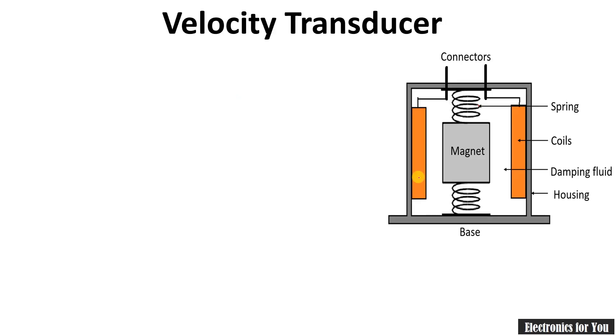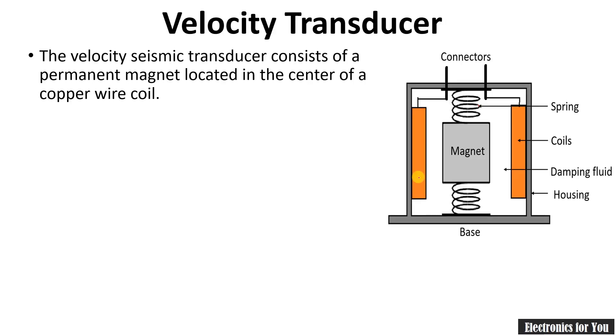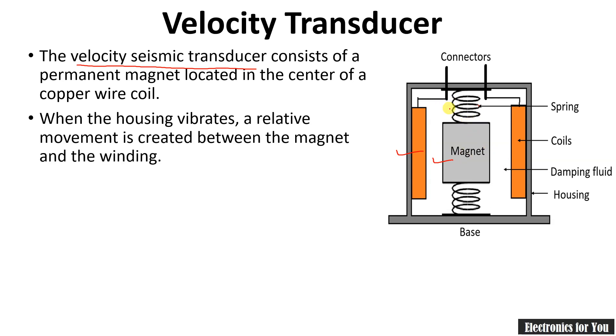Now let's see the velocity transducer, also known as the velocity seismic transducer. This transducer consists of a magnet and a coil around the magnet. The magnet is installed on a spring. The working principle of the velocity transducer is based on Faraday's law of electromagnetic induction, because this construction is generally used for generators.